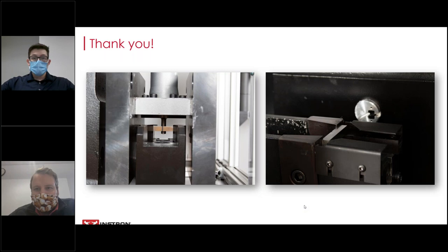Yeah, so depending on your provider, you may or may not be able to. For example, with the 750 option MPX that Instron provides, you can change your fins, which is what make up the U design, to be a smaller weight, and you can do that to get more precision if you want to get further down than what your machine is rated to. For the most part, the encoder allows us to test down to very low values, but you can certainly change out your equipment if you want to get even more precise than that.